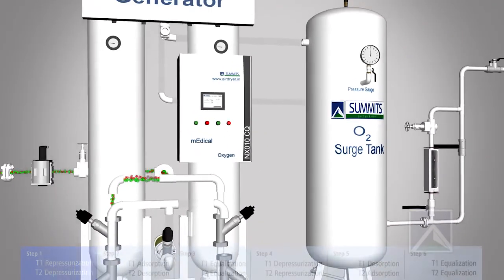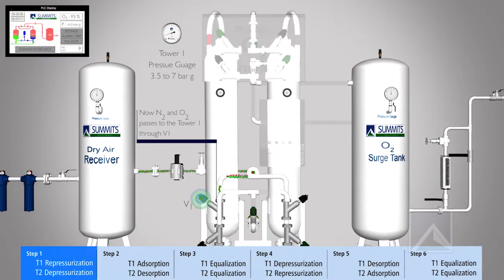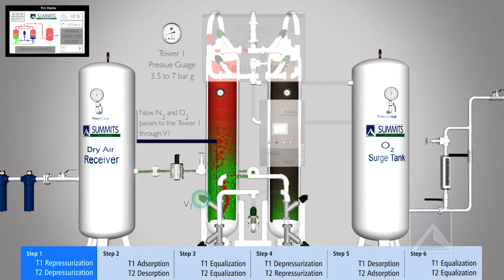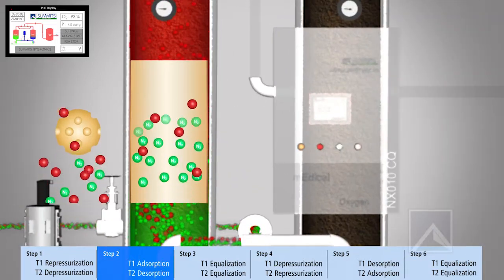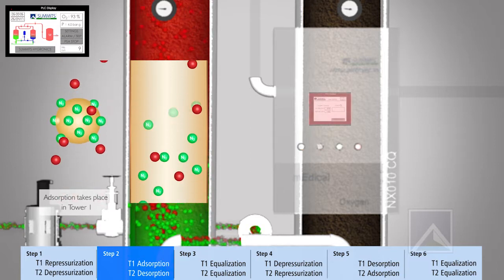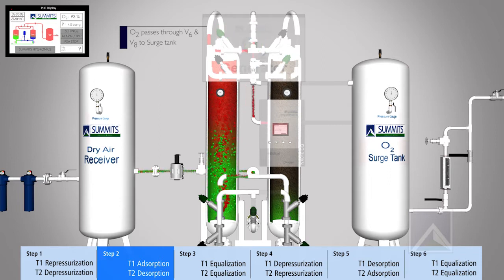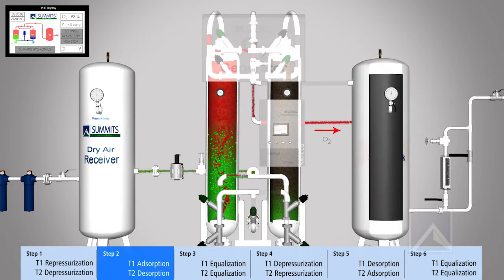As Step 1, pressurization occurs in Tower 1 and depressurization in Tower 2. After Step 1, the highly adsorbable synthetic zeolite adsorbs nitrogen from the dry air in Tower 1, and simultaneously oxygen is stored in the surge tank.